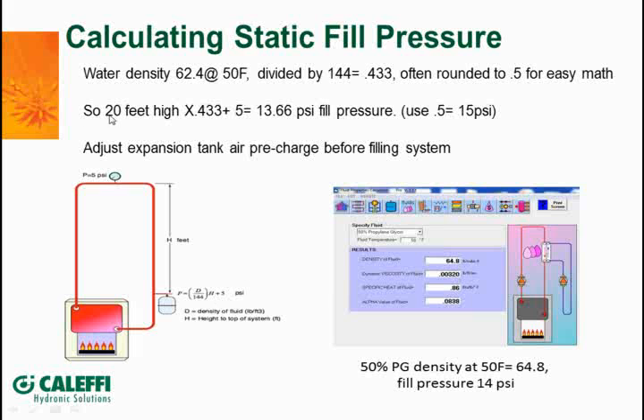So if you put that in the formula, we've got a 20-foot high building times .433, plus the 5 pounds that we want at the top point here. So that's going to give us a 13.66 psi fill pressure to make sure that we've got the 5 pounds on this 20-foot of lift here.